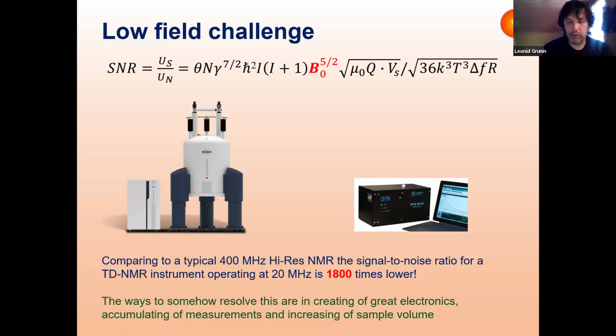But you know why time domain NMR is becoming more and more popular? That is because the electronics and technology are evolving and becoming much better. Comparing the signals we are getting now with one scan to what we could get 25 or 30 years ago, it's just incomparable. So let's say this problem is somehow being solved. The other thing is that normally in high resolution you use small test tubes, because you need to provide a uniform magnetic field in a small volume. In a time domain NMR experiment, you can use much bigger tubes, and the amount of sample is larger. So you also resolve the issue with the signal-to-noise ratio.